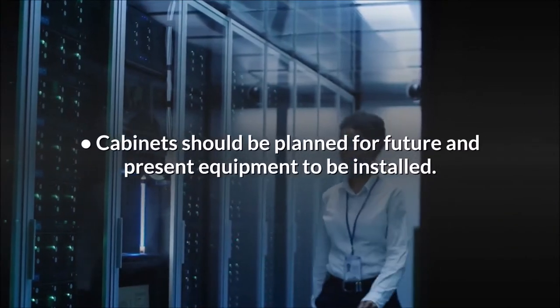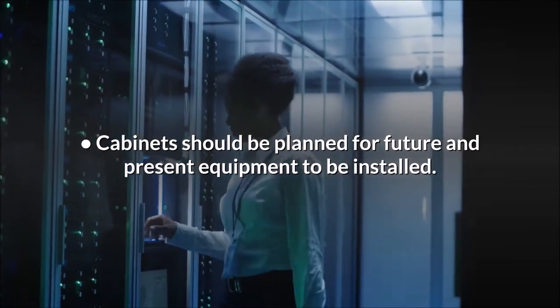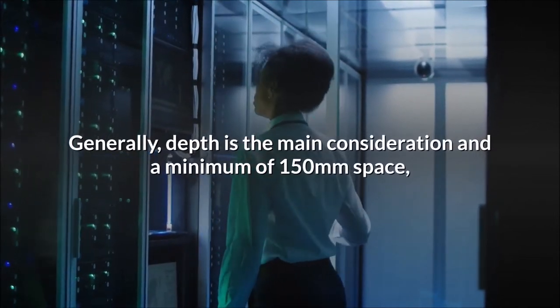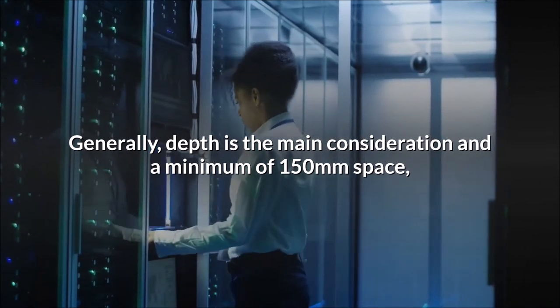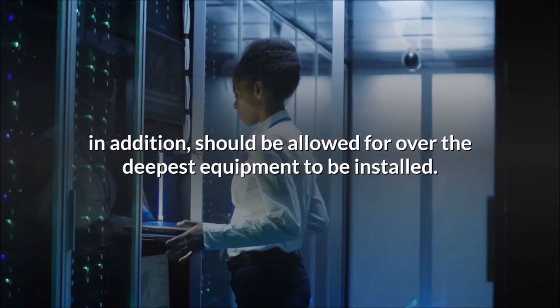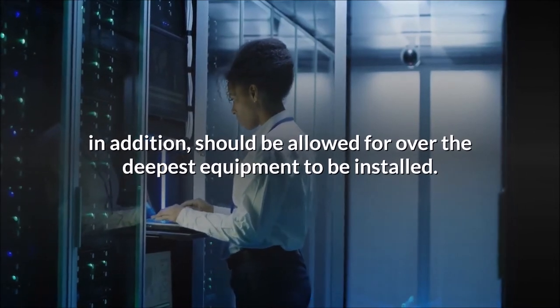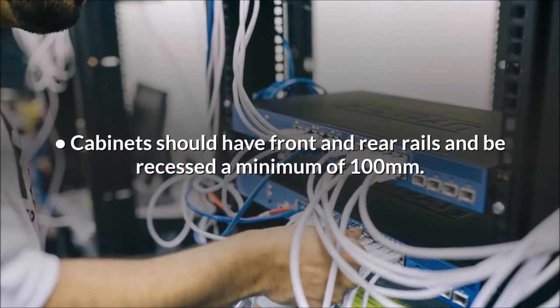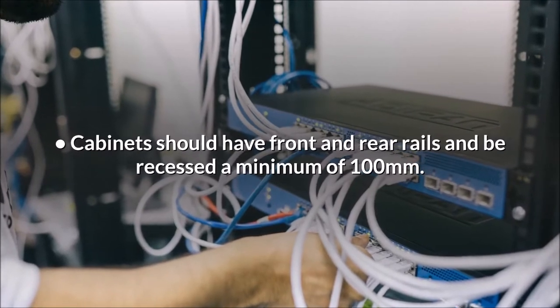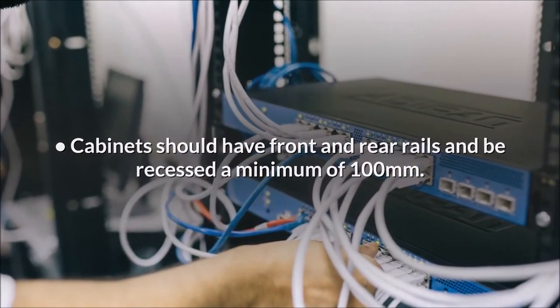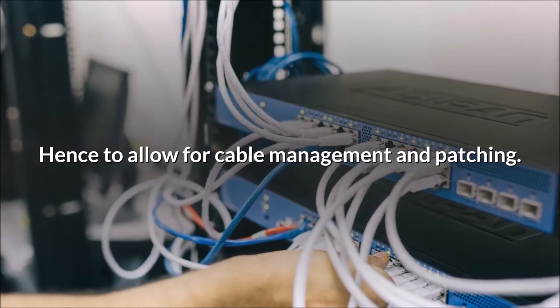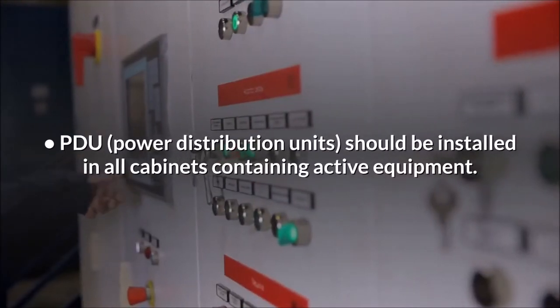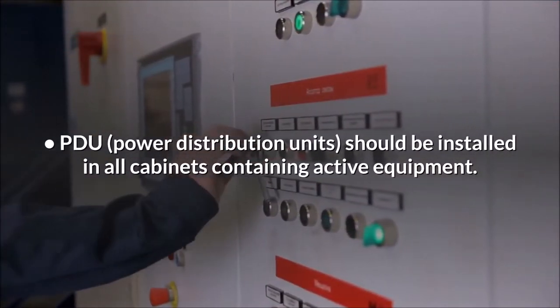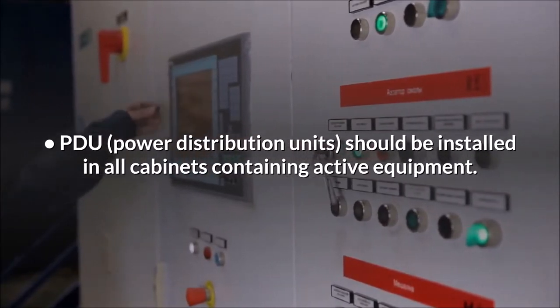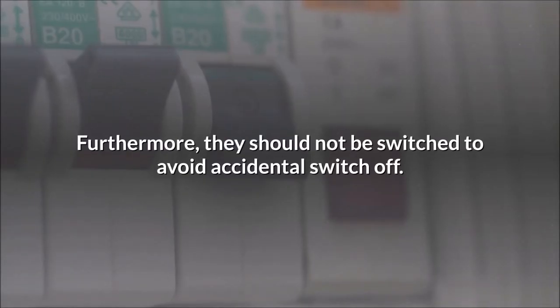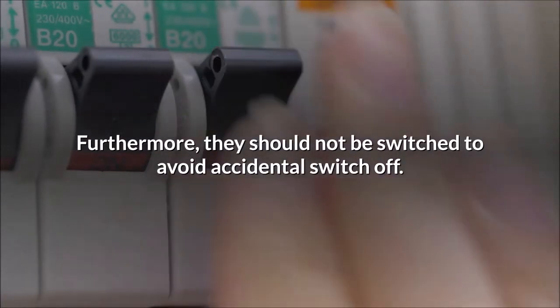Cabinets should be planned for future and present equipment to be installed. Generally, depth is the main consideration and a minimum of 150 mm space, in addition, should be allowed for over the deepest equipment to be installed. Cabinets should have front and rear rails and be recessed a minimum of 100 mm, hence to allow for cable management and patching. PDU, power distribution units, should be installed in all cabinets containing active equipment. Furthermore, they should not be switched to avoid accidental switch-off.